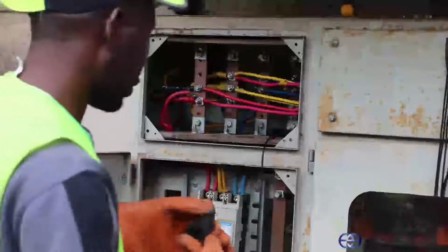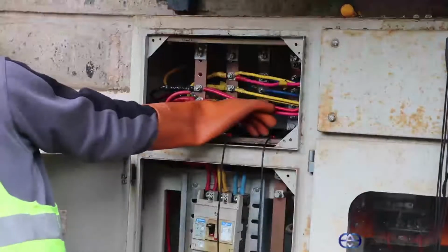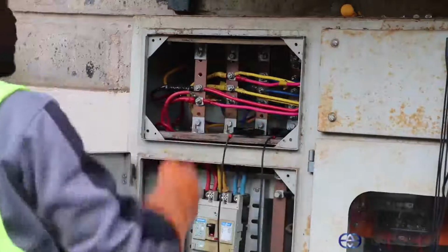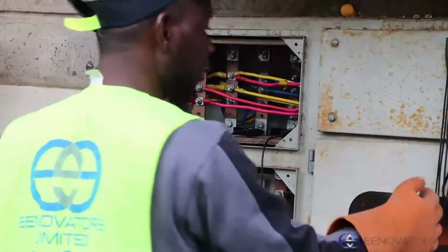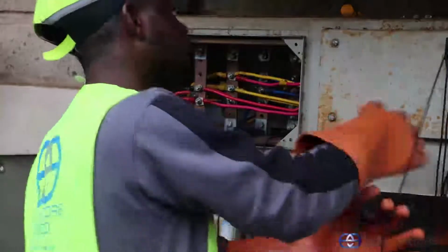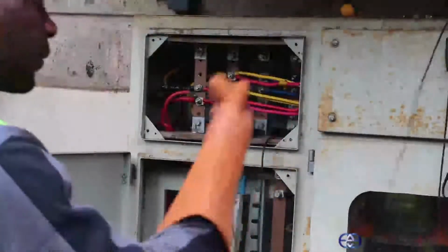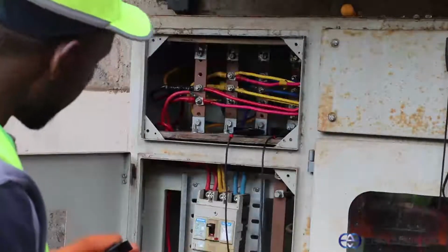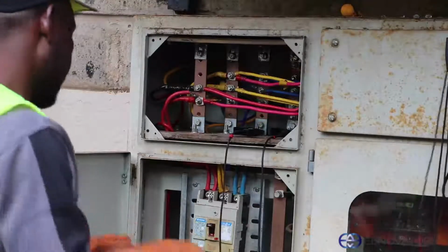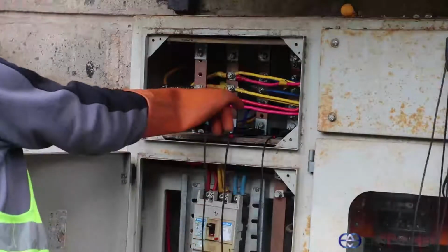So that one goes into a crocodile clip. Then carefully I just put it there. So remember, with these gloves you can handle voltage of up to 18 kV. So that's why I'm not worried. I'm sure I'm working at 415 volts. So with this I'm more safe. So I go to the middle phase, or second phase, or the yellow phase. I plug it in.